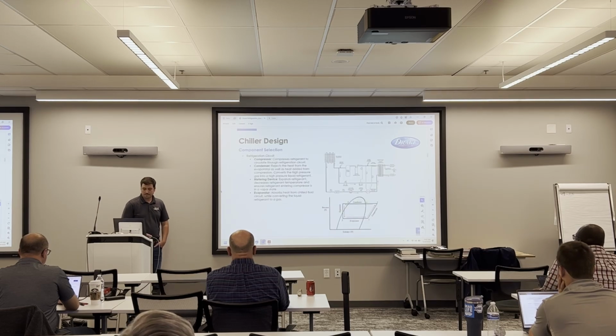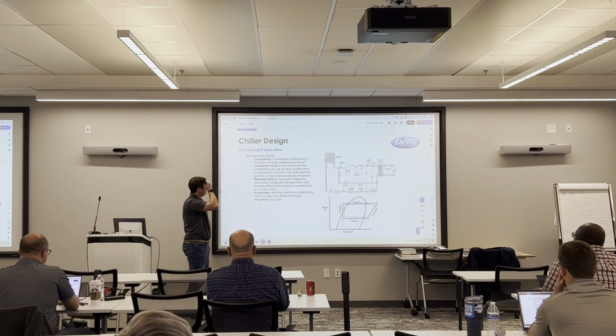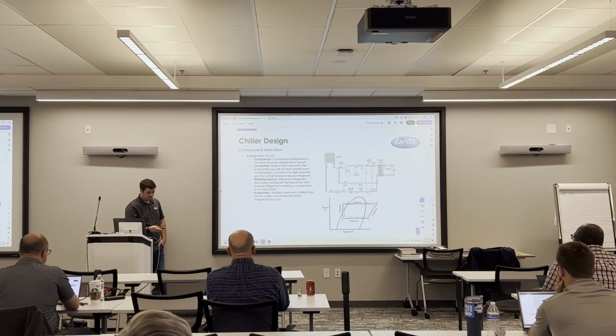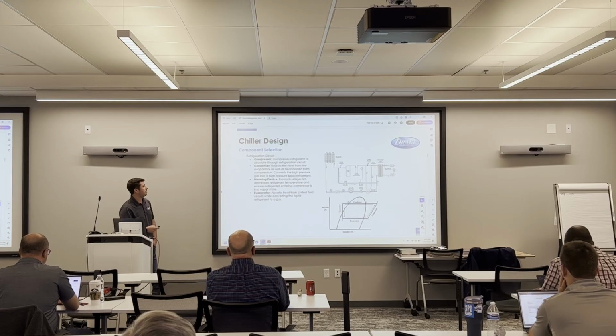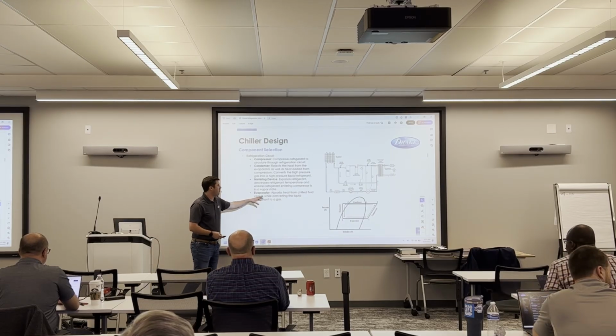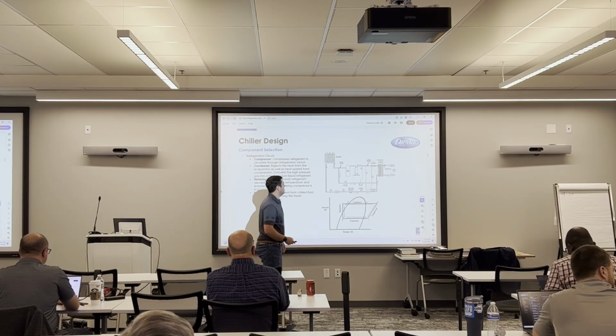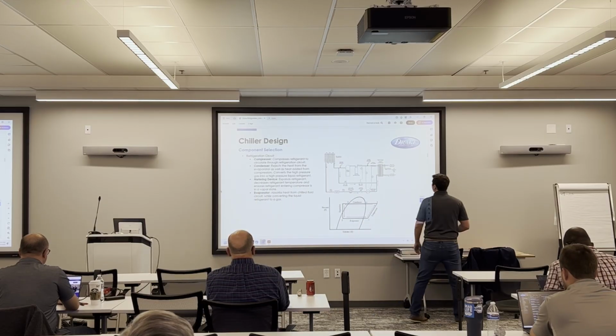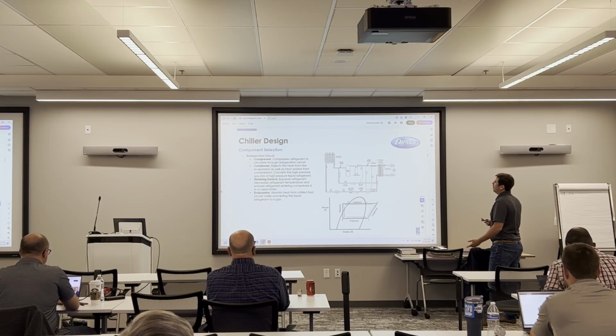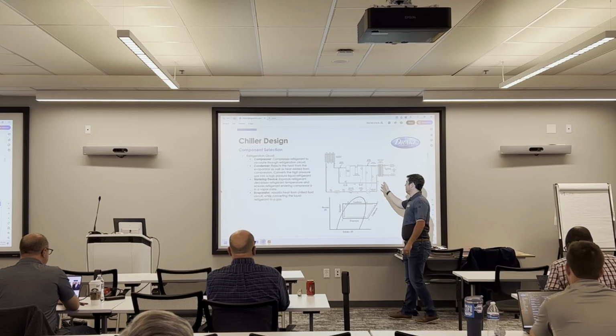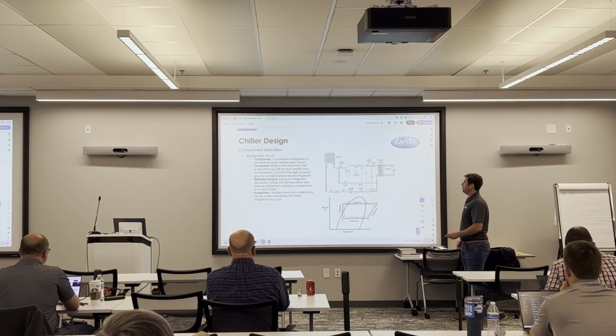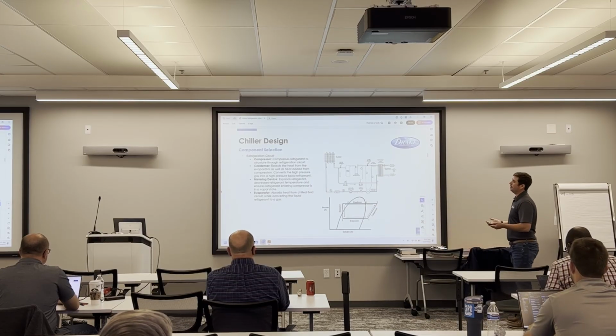All right, so now we'll talk about what goes into our component selection. Again, just highlighting the 4 major components here: you've got your compressor, the condenser, your metering device, and your evaporator. We'll start with the evaporator. Just a recap from our previous slides: your evaporator is just your cooling medium. You're going to have water, or glycol, or rocket fuel on one side, and then cold refrigerant on the other. The purpose of the evaporator is to absorb the heat from the chilled fluid circuit while converting that liquid refrigerant to a gas, like your superheat.